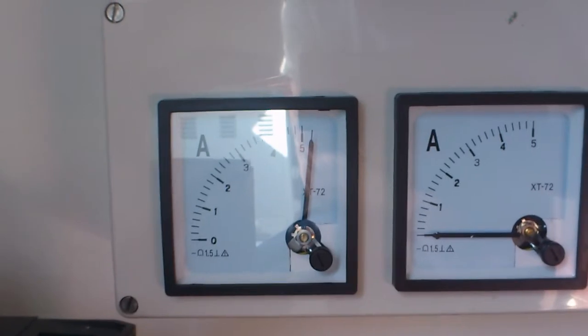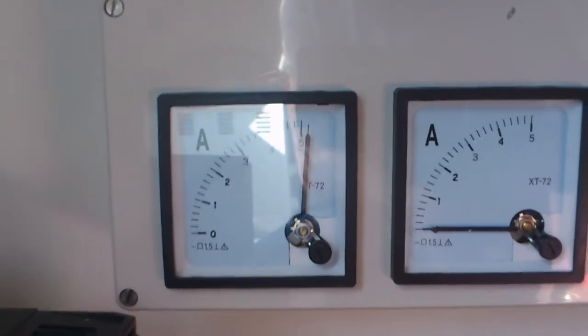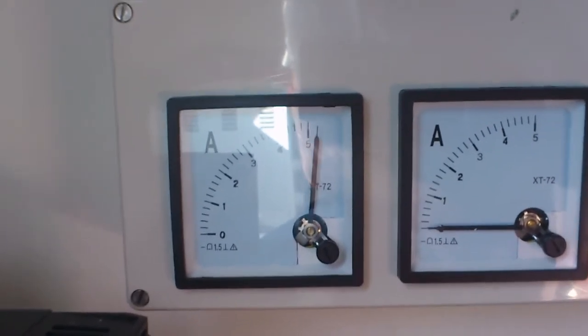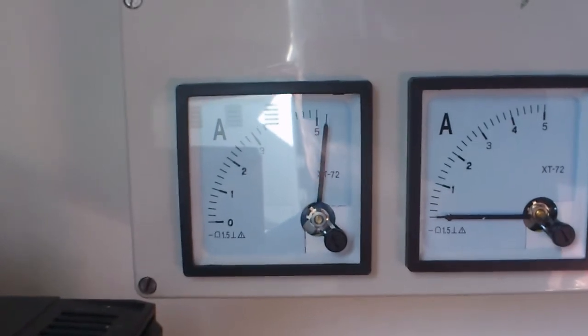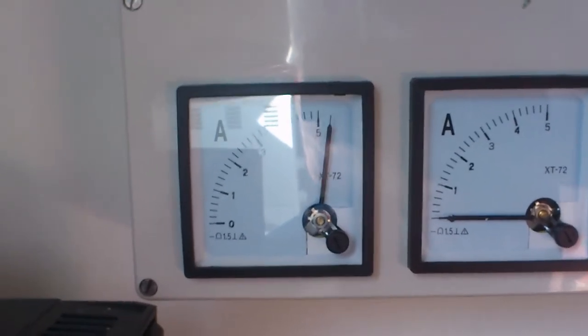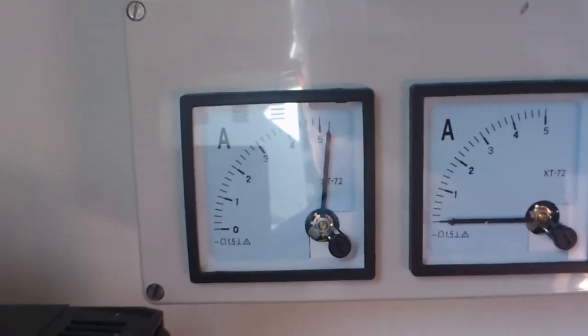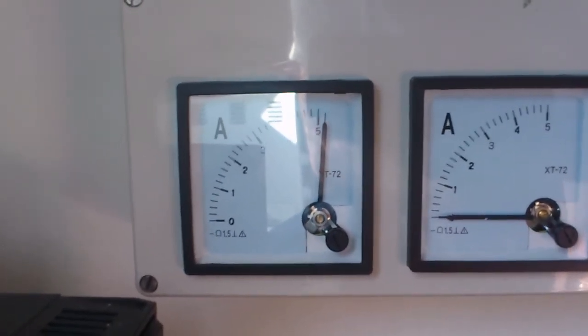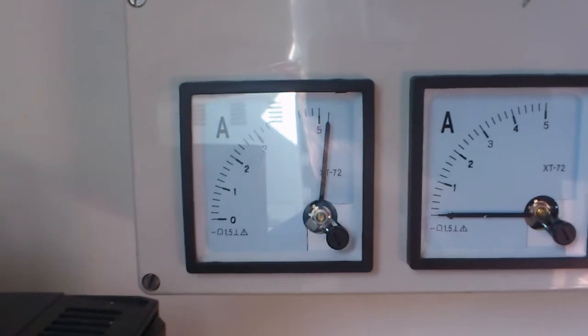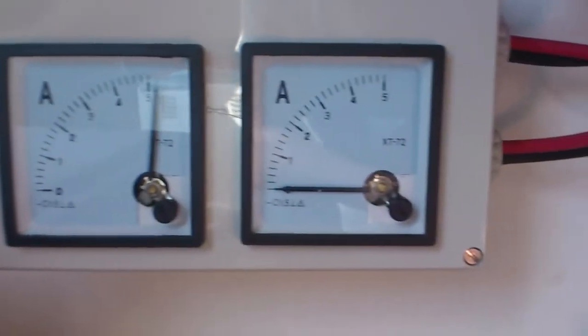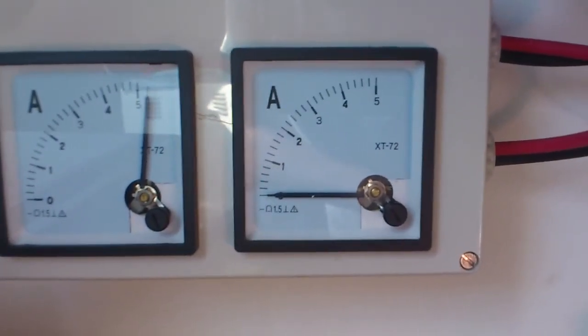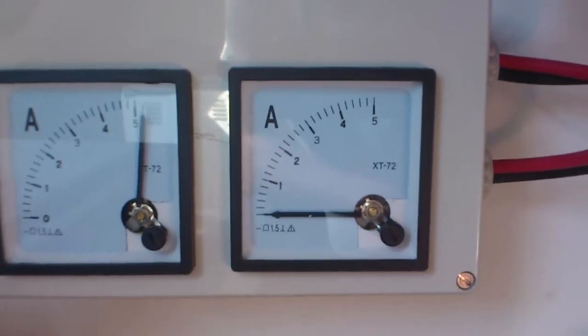So don't be surprised if you actually see six or more amps from a five inch cell, something to keep in mind which the normal data sheets of panels will never tell you. Now the meter on the right, which is my west string, is currently at zero.